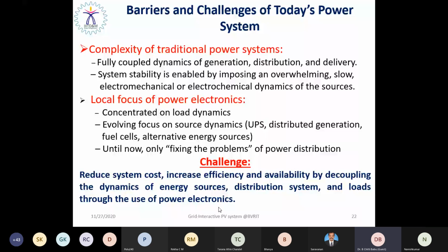That is why we use virtual energy storage, like introducing energy storage. Even a solar PV system cannot be used alone without energy storage. Especially for a standalone system, we invariably use energy storage along with the solar PV so that it can provide uninterrupted electrical power to the isolated and standalone system. And the focus of power electronics has so far been on load dynamics, especially in industry for adjustable speed drives. Now the scenario has changed: the source is also an intermittent, distributed energy source. So the power electronics has to be used between the source as well as the load to improve the dynamics of both.